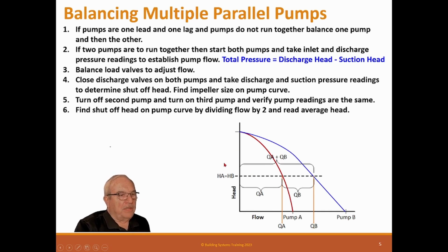When you have multiple pumps running together, parallel pumps, you need to request a multiple pump curve. Normally a pump curve is for one pump, and this one here would be one pump. So this would be the shutoff head right here, and this would be the total flow of the pump at no head. So you can see that's the one pump curve. Well, we have two pumps, and since they run together, we need the second curve, which is the second pump, which is the same head, right? And it goes out here. So the no head flow from A to B is the same as from 0 to A. So these are equal here, but as this curve comes back up, and I didn't draw that very well, these change position. What I'm trying to tell you here is that this GPM is less than this GPM.